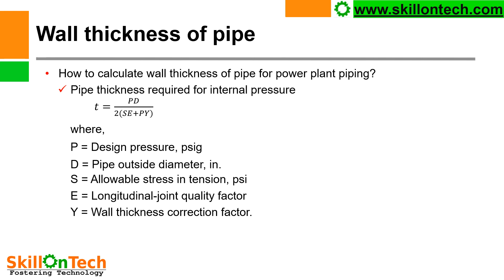Wall thickness of pipe — how to calculate wall thickness of pipe for power plant piping? The pipe thickness is required to resist internal pressure. The formula for calculation of thickness is: T = PD / 2(SE + PY), where P is design pressure, D is pipe outside diameter in inches, S is allowable stress in tension (PSI), E is the longitudinal joint quality factor, and Y is the wall thickness correction factor.